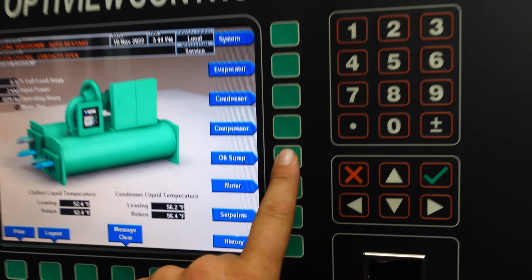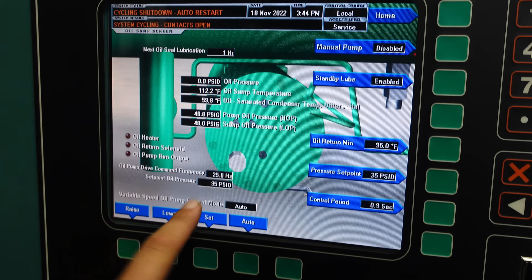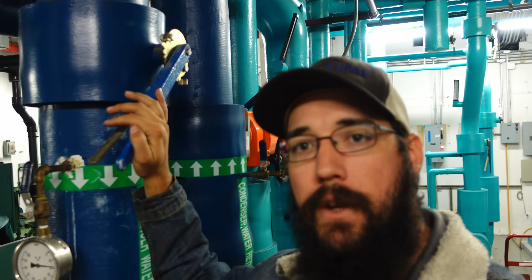The charge is done. We are ready for startup. And come over to our oil screen. Up to 112 on temp, that's good. We're not even calling for the heater. We need to go up and shut down the temporary chillers. So far we've got the valves, everything open back up and balanced on this chiller. When we turn those off, we'll close the ISOs here in the plant, and that'll get our water shut off so that we can then focus the water on this chiller like we need to.